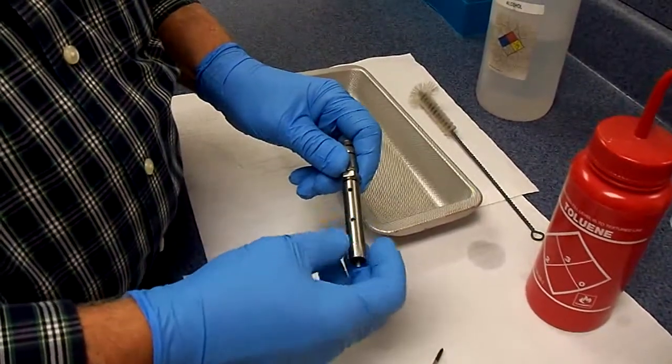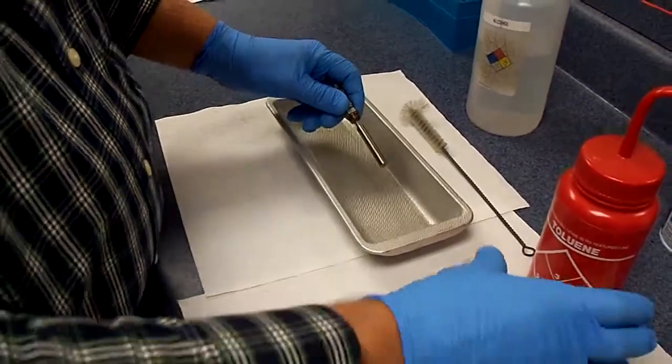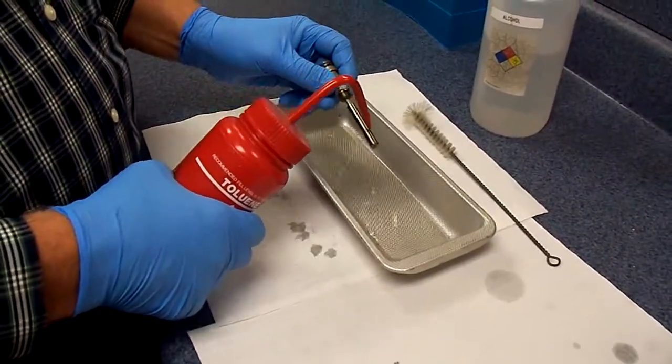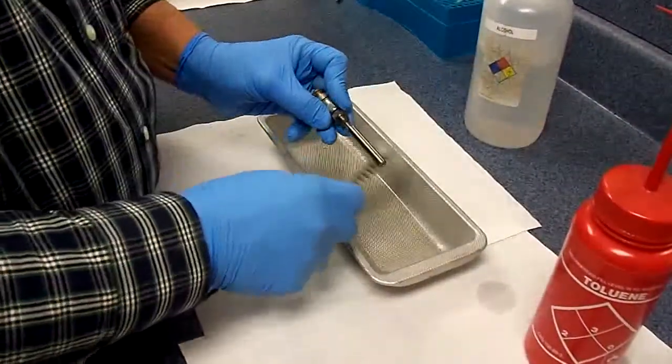Unscrew the outer electrode. Rinse with Toluene. Scrub it a little bit.